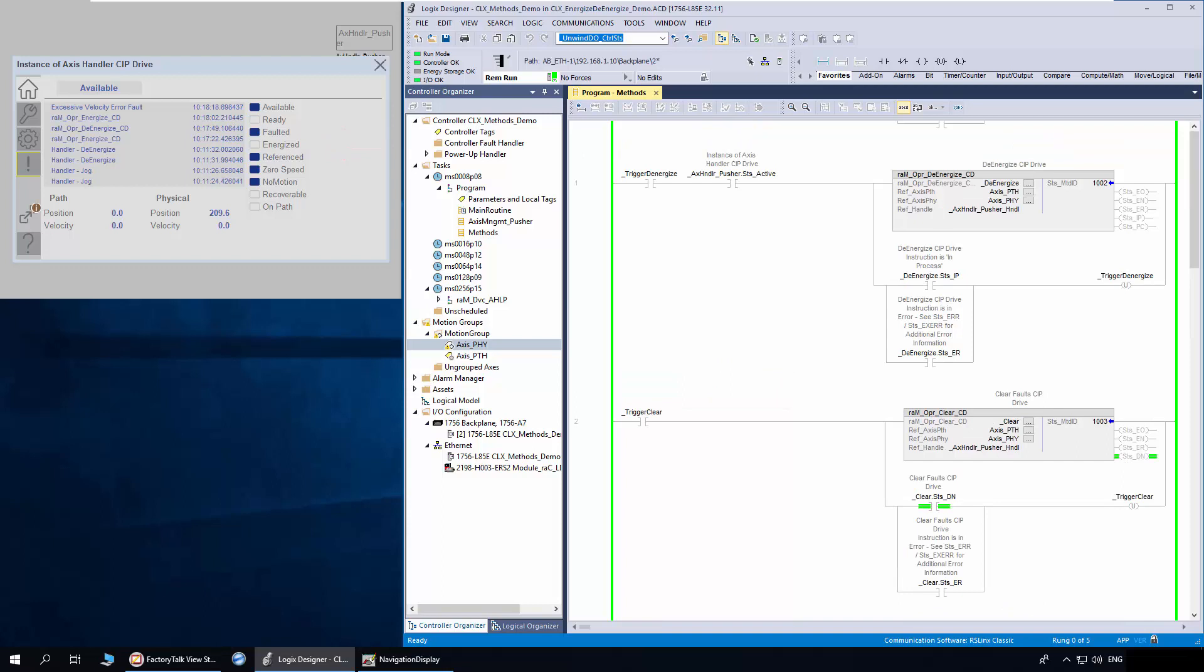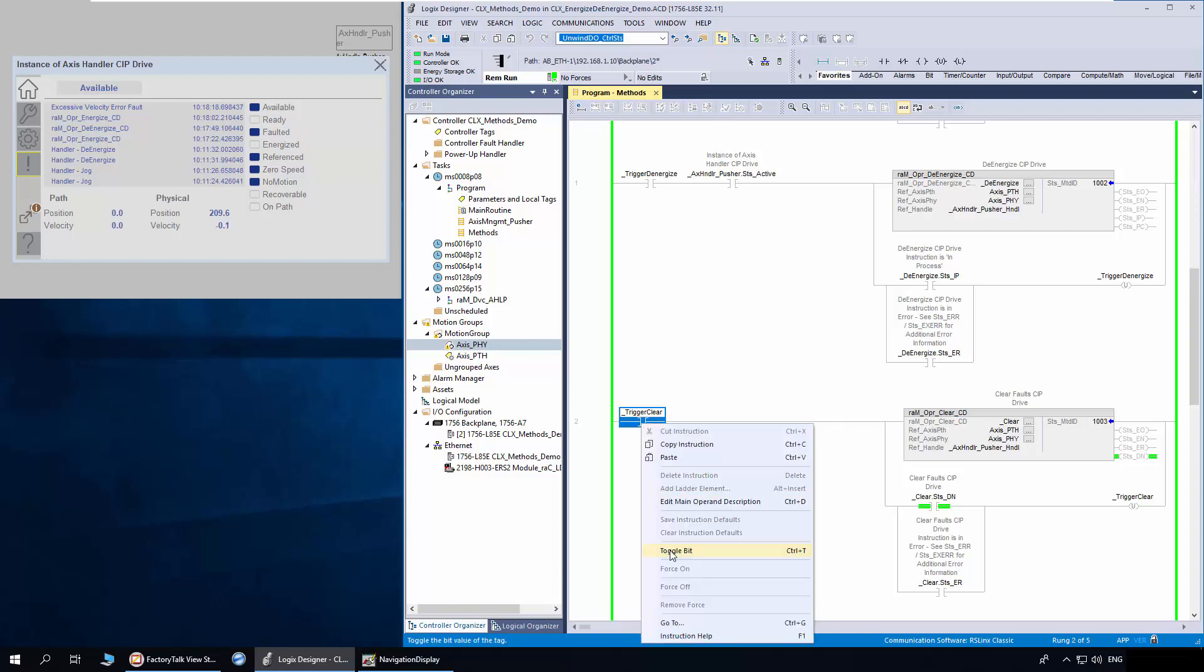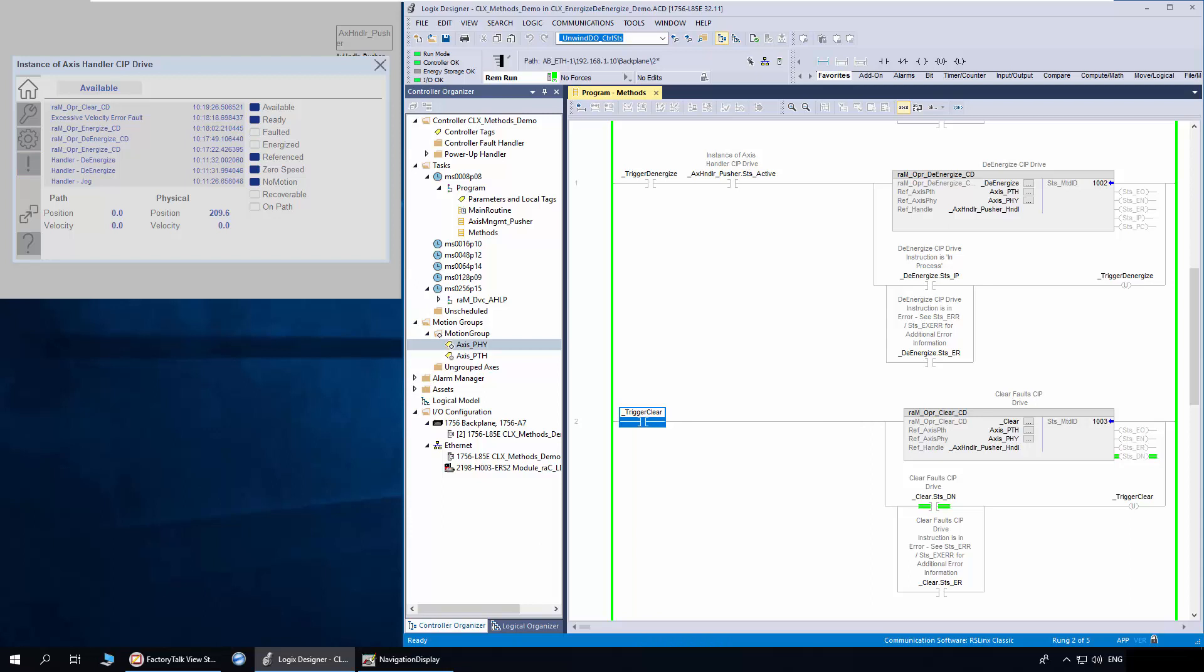To demonstrate the Clear method, I have created a fault in the physical axis. Thus, the handler status is showing faulted. I will trigger the Clear method to clear the axis fault. Now the physical axis fault is cleared and the faulted status bit is turned off.